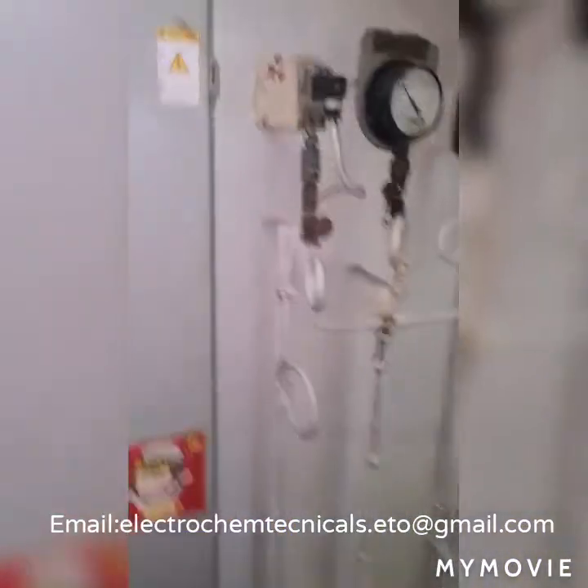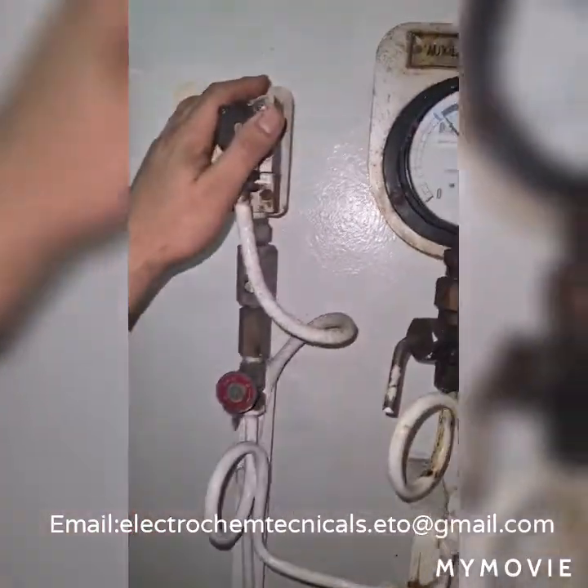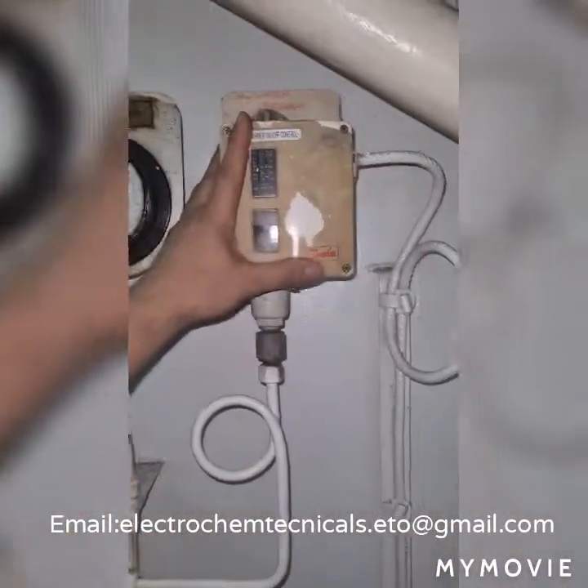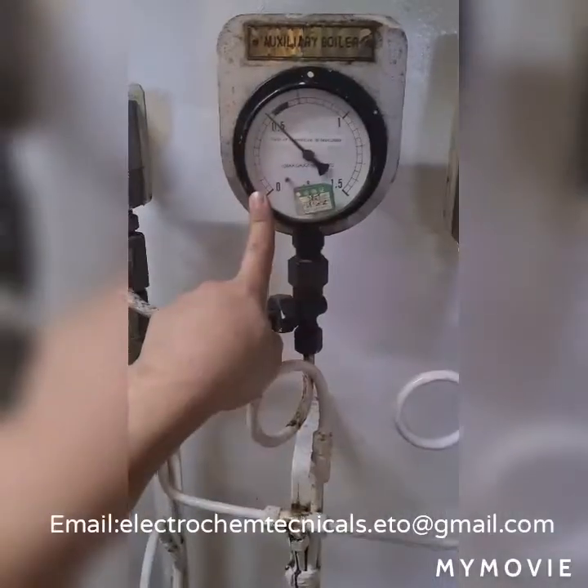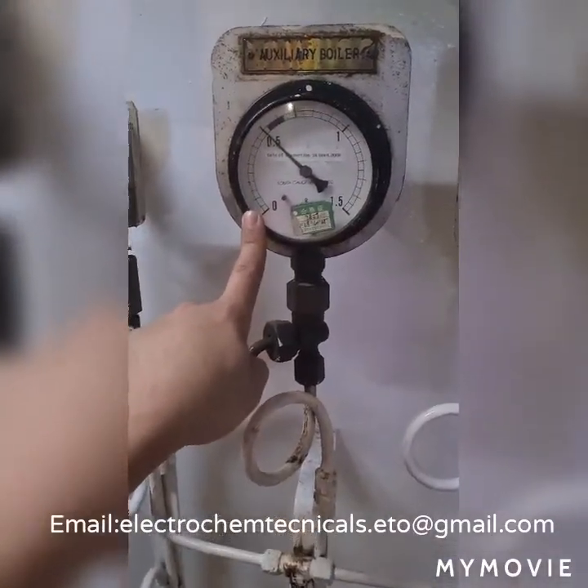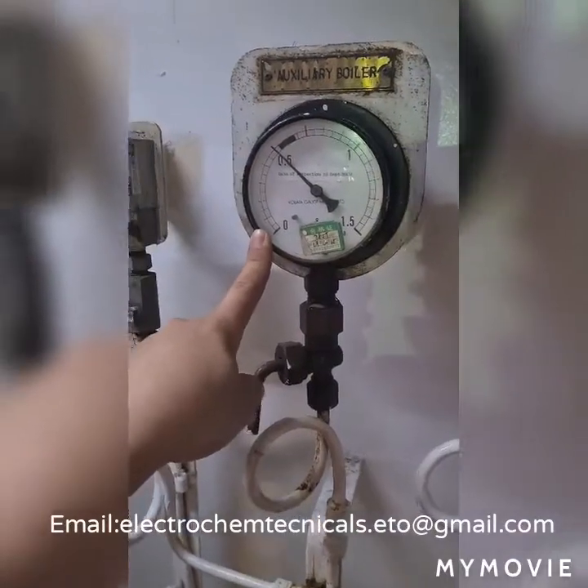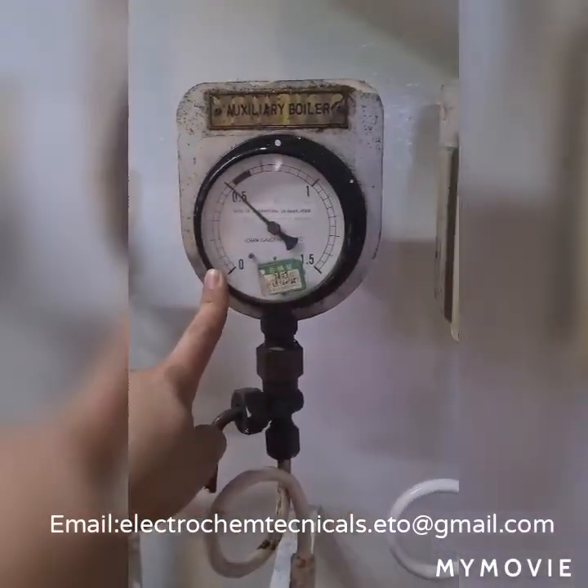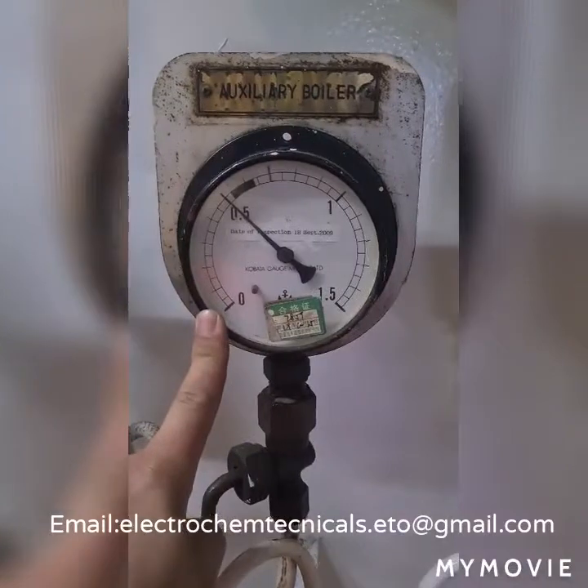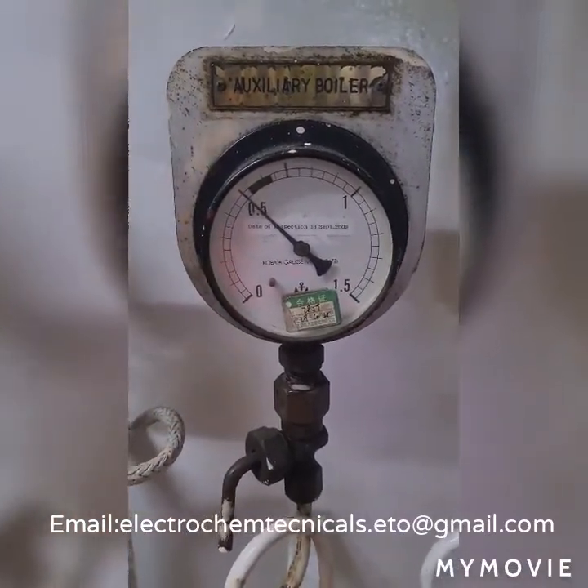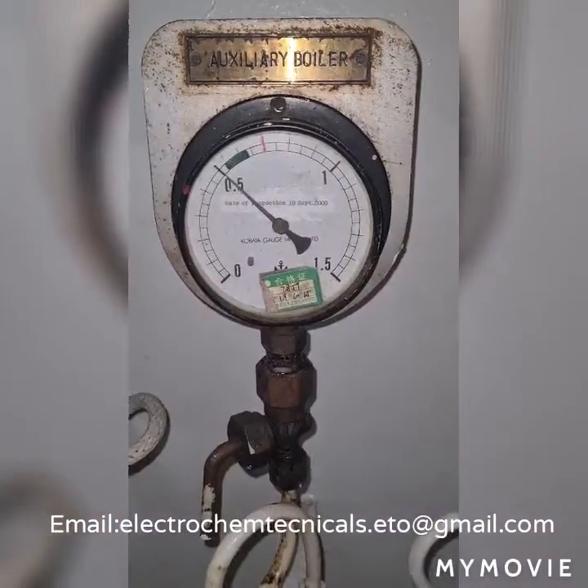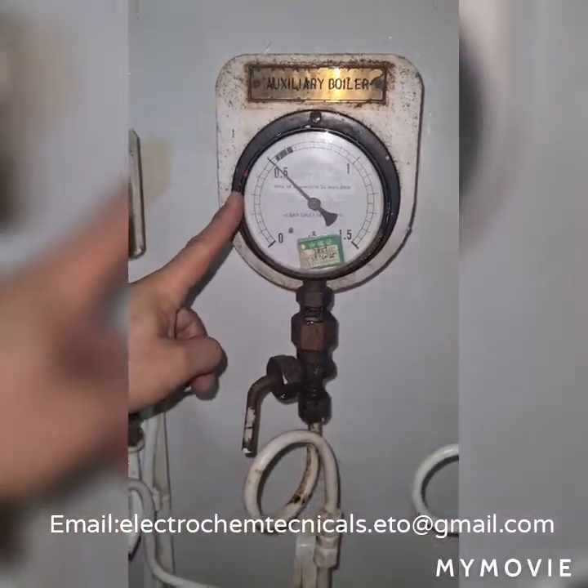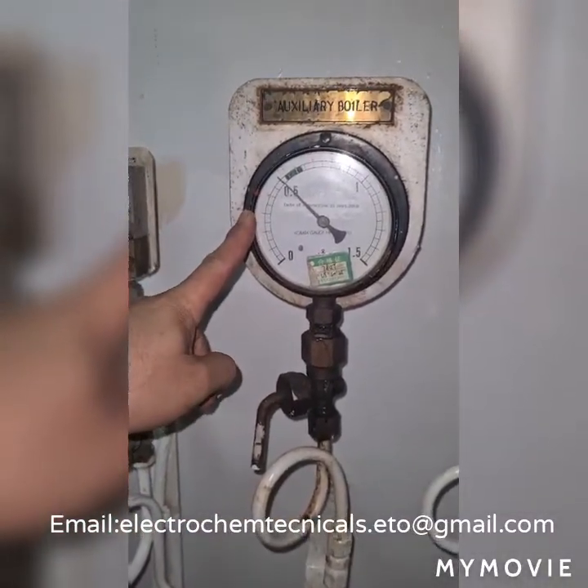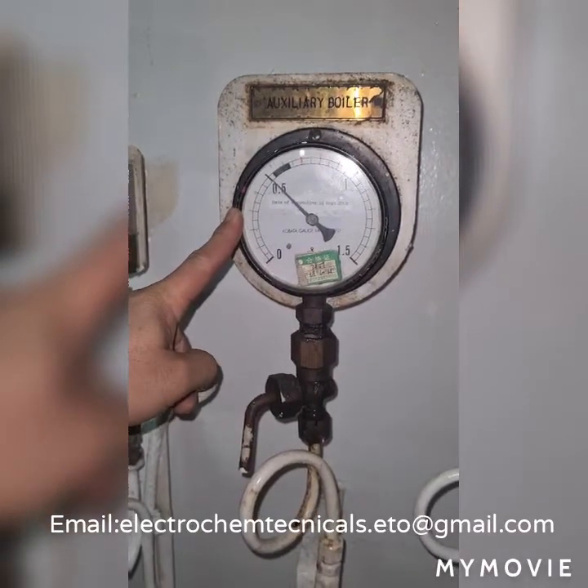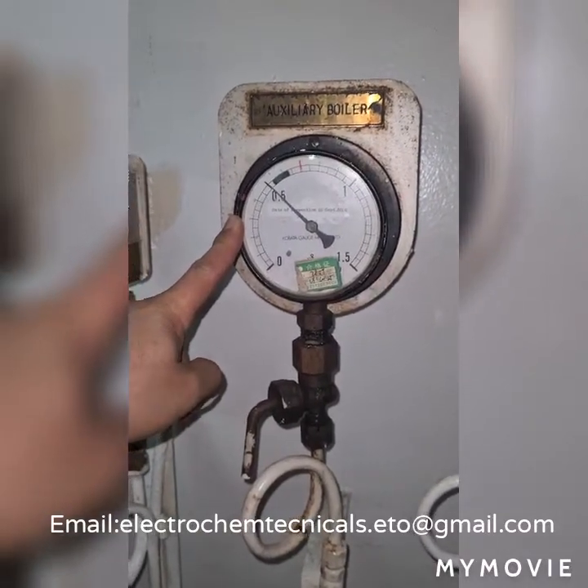And here we have also the pressure transmitter, the pressure gauge, and the pressure switch of the boiler. As you will find here, the steam pressure becomes less than 0.5, around 0.45 megapascal. This is the steam pressure now. The boiler needs to start automatically at 0.45 megapascal.